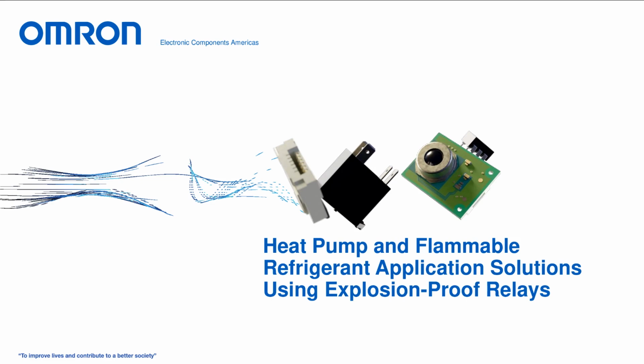Since we're on the topic of currents, I'm going to jump in with my own question here, just to feed off that last one. Why is 16 amps the kind of magic thing between sealed and unsealed for relays? So that's also a good question. When the current exceeds 16 amps, the potential for sparking or arcing increases. So that's in accordance with IEC, that's the level in which we start to have that concern. We probably won't see true problems until maybe 20 amps, but with that factor of safety, we want to give a number to be the threshold to cut off, so we have that full isolation from the semi-flammable gases. So it's really developed by the IEC as that level of dangerous arcing potential.